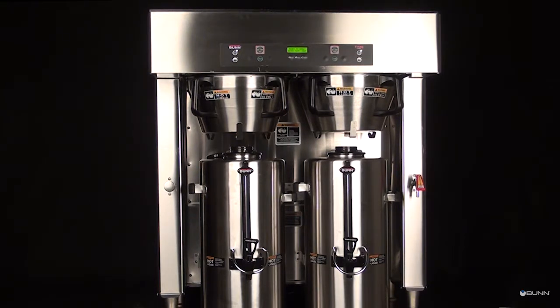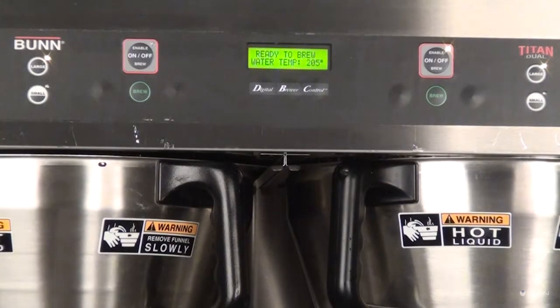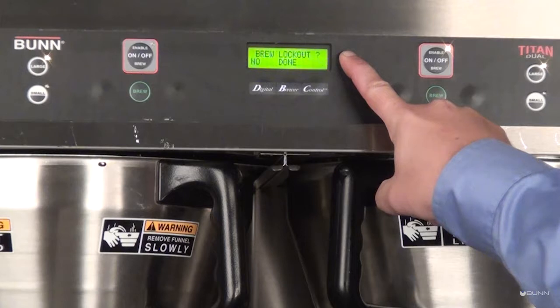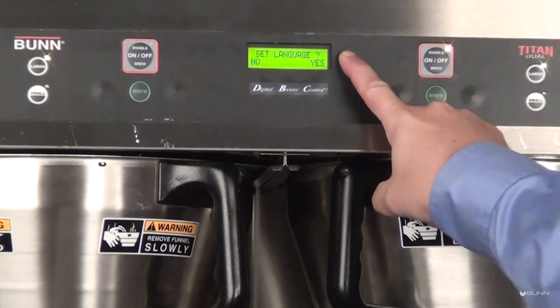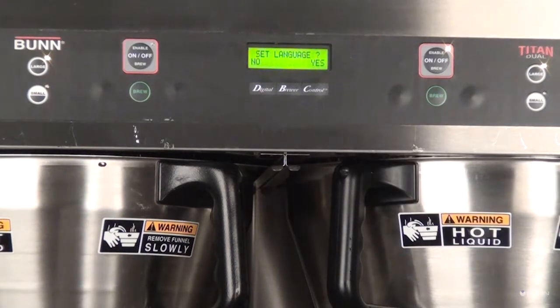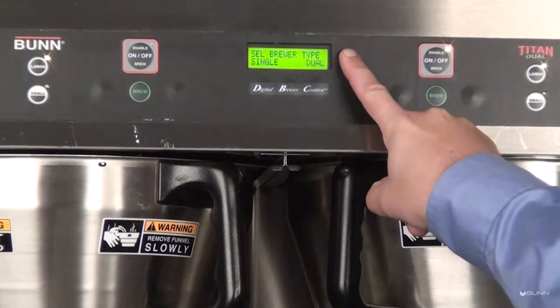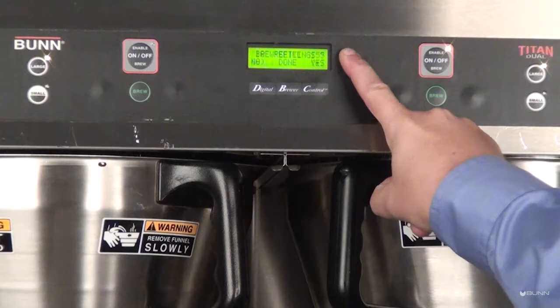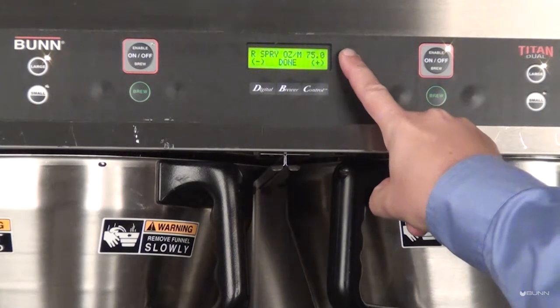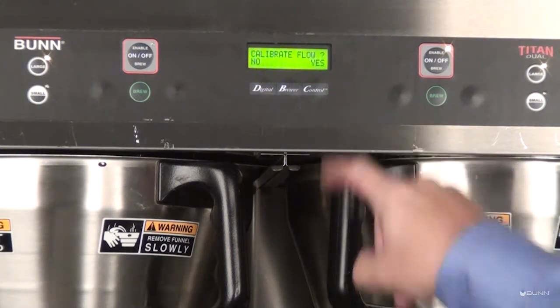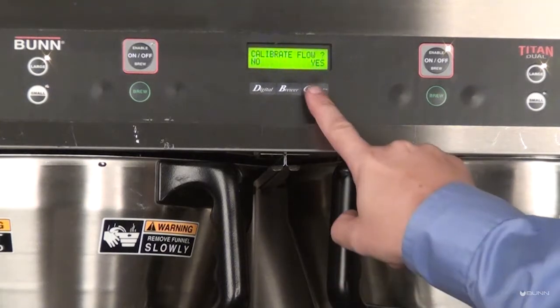If you would like to test and enter the actual flow rate, locate the hidden switch to the right of the digital display screen. Press and hold the switch until the display screen reads set language. Press and release the right hidden switch until Calibrate Flow appears on the display screen. Select Yes with the control switch.